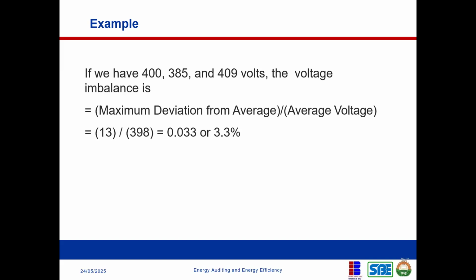Now we want to calculate the voltage imbalance across this line. We have 400, the standard voltage, 385, which is lower than standard, and 409, which is higher than standard. So how do we calculate the voltage imbalance? The same way we did in the previous example: we find the average of the three phases, subtract that average from each voltage to determine the deviations, identify the highest deviation, and divide it by the average.